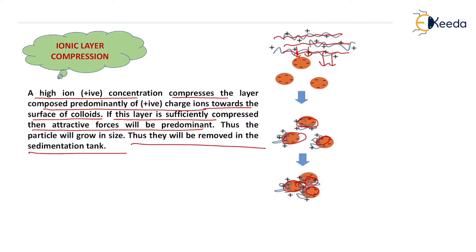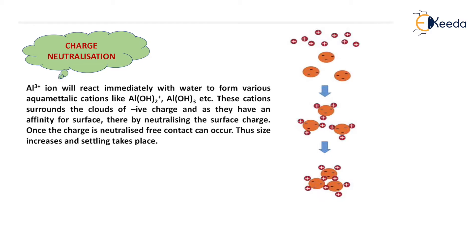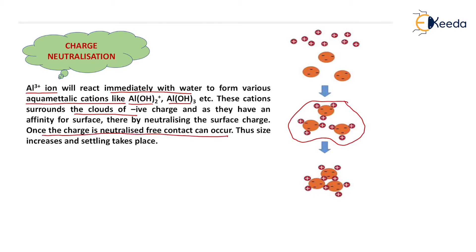In all the mechanisms, charge neutralization takes place and particle will grow in size and be removed later in the secondary sedimentation tank. The second mechanism is charge neutralization. Alum added in the water as coagulant reacts immediately with water to form various aqua metallic cations like Al(OH)₂⁺ as well as aluminium hydroxide Al(OH)₃. This positive charge surrounds the clouds of negative charge and as they have affinity for the surface, thereby neutralizing the surface charge. Once the charge is neutralized, free contact can occur, all the particles come in contact with each other and grow in size, and settling takes place.